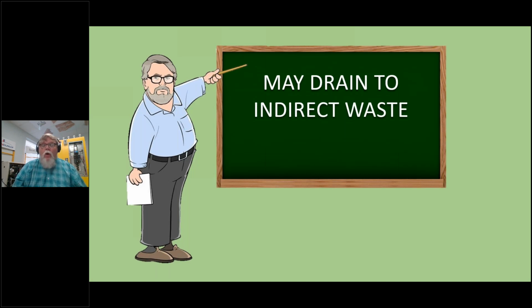We actually do drain to wash machine drains in some areas. Other areas, they may say, no, you can't do that because we don't want to treat your condensate water through our sewer system. So you kind of have to figure out what the local authority is allowing, but an indirect waste is pretty common. Here in Virginia Beach, we almost always drain out on the ground. Pipe pops out the back of the house somewhere, turns down with an elbow. Otherwise, it can run back into the wall. Turn down with an elbow, and we drain down onto the ground.